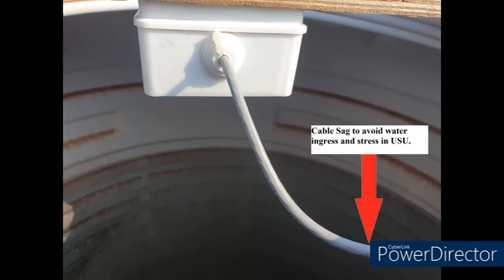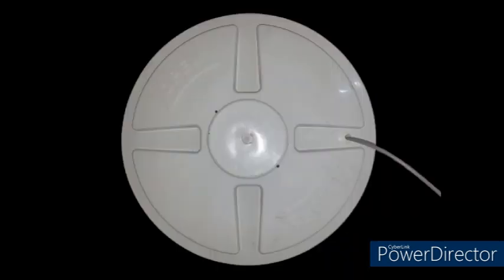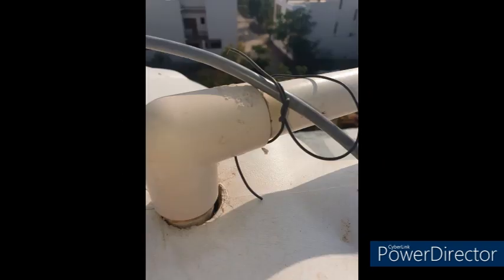Remember, it is very important to place the rubber grommets at both holes and to leave the sag, loop to avoid water entry to USU, as the presence of water in USU will void the warranty of the device. Once the USU is mounted, the lid sheet is securely placed on top of the tank with USU facing tank bottom and cable outwards. Outer cable must be secured to a nearby structure to avoid stress on cable and USU. In case your delivery pipe in the tank has not got a UPVC T, please install it as per the size of your delivery pipe.